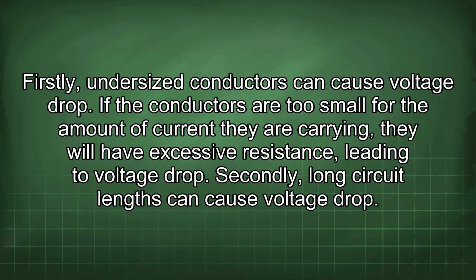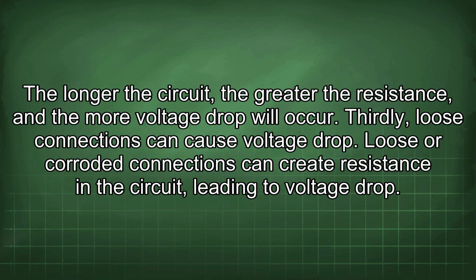Firstly, undersized conductors can cause voltage drop. If the conductors are too small for the amount of current they are carrying, they will have excessive resistance, leading to voltage drop. Secondly, long circuit lengths can cause voltage drop. The longer the circuit, the greater the resistance, and the more voltage drop will occur.